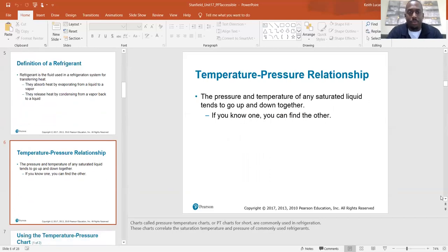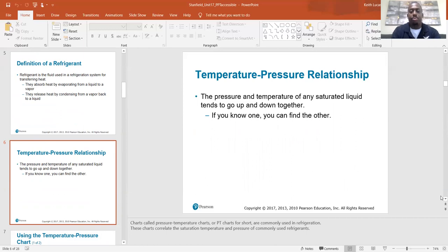Temperature-pressure relationship: the pressure and temperature of any saturated liquid tend to go up and down together. If you know one, you can find the other. Charts called pressure-temperature charts, or PT charts for short, are commonly used in refrigeration. These charts correlate the saturation temperature and pressure of commonly used refrigerants. The PT chart is something we're definitely going to get a chance to play with.